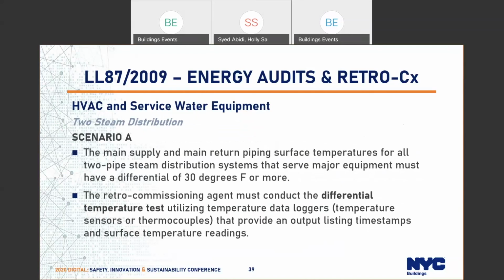For two-pipe steam distribution systems, there are two scenarios that have been listed. In scenario A, if the retro-commissioning agent can demonstrate that the supply and main return piping surface temperatures for all two-pipe steam distribution systems that serve major equipment have a differential of 30 degrees Fahrenheit or more, then there is no need to conduct steam trap testing.